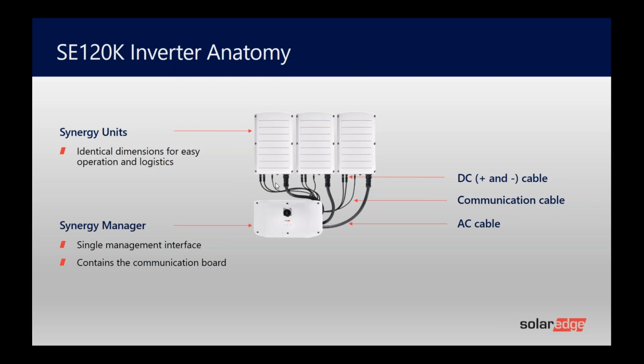And what it means is there are a couple of advantages of this approach, as opposed to a monolithic inverter or a string inverter or a central inverter. You have more uptime capability, right? So if there is an issue and one of the engines goes down, in this case, you lose 40 kilowatts as opposed to losing 125 or 150 kilowatts, depending on the inverter that you're using on your project.